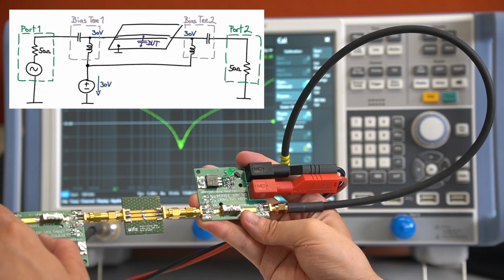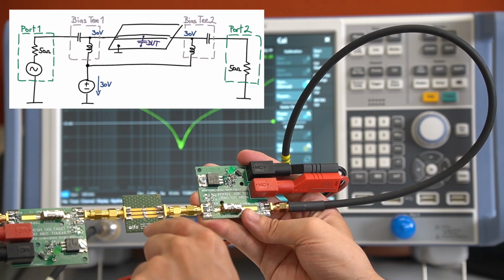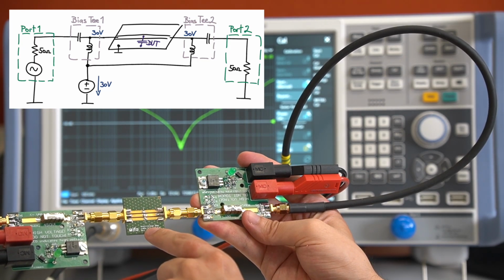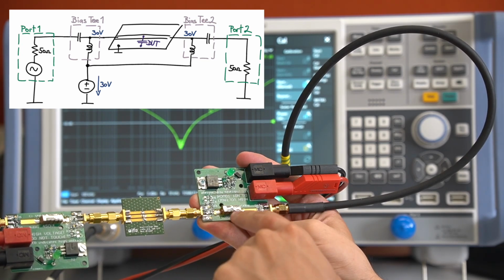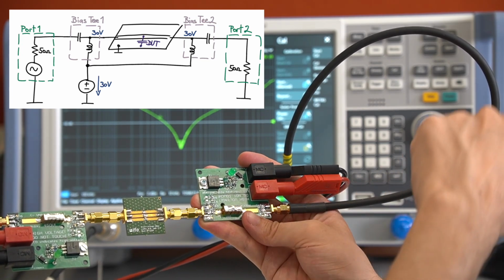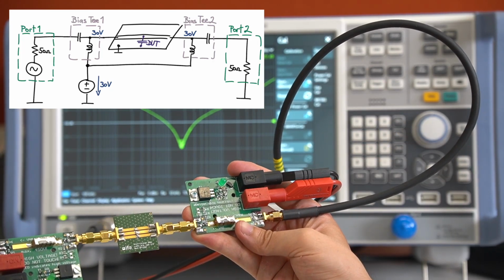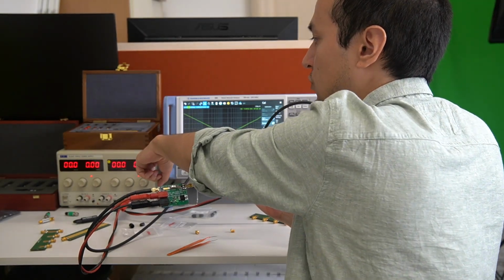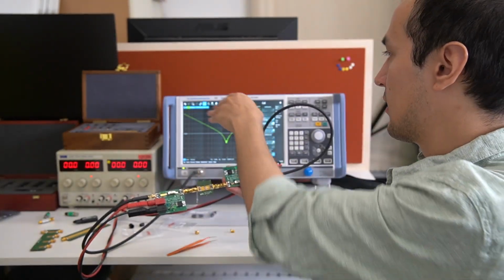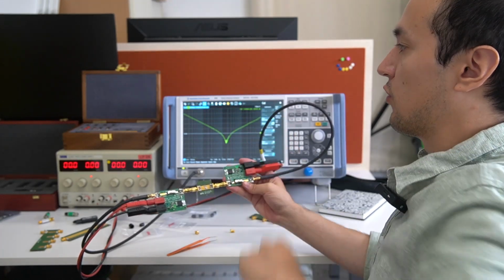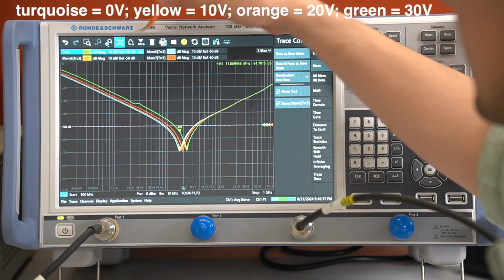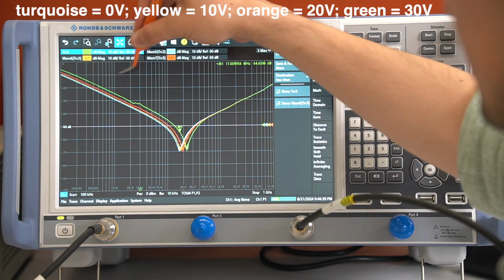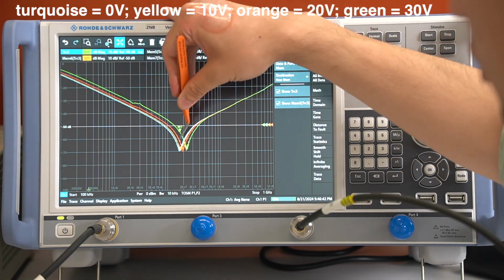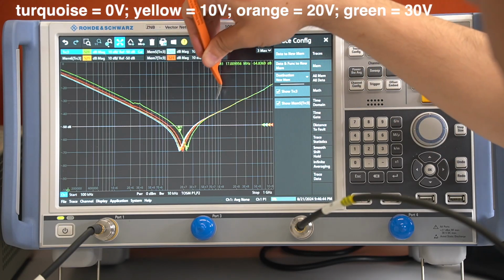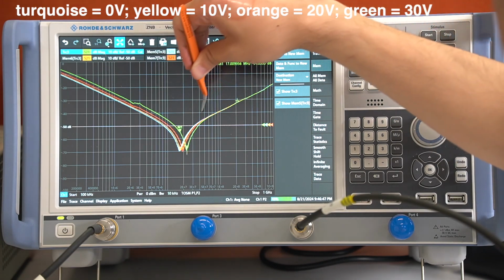Okay, this is our test setup. Here we have port 1, then the bias T, then here we have our 200 nanofarad device under test, second bias T which directs here to port 2. And now I have here my power supply, and I will increase the voltage now, and then we check how this impacts our impedance curve. And you can see the higher the voltage, the less capacitance value we see here, resulting also in a shift in the resonance frequency, but the inductance value stays the same.